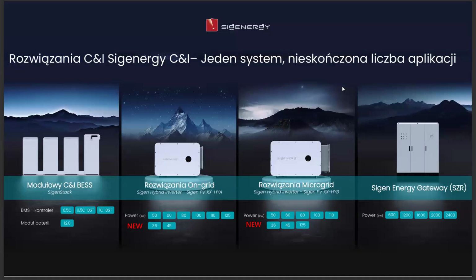3. Commercial segment and zero export. In large commercial systems, for example, a 100 kilowatt grid connection with 500 kW PV on the roof, the challenge is how to manage energy so that not a single kilowatt is exported to the grid when export is not permitted. Sigen handles zero export with high precision. Regardless of system size, our platform accurately controls the power delivered to the building. This allows the customer to oversize the PV installation to improve production on cloudy days, and on sunny days either store surplus energy in batteries or charge an EV fleet, all without the risk of penalties for unauthorized export.